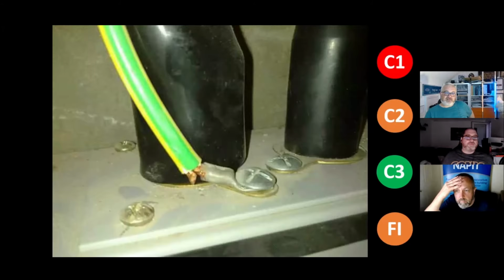I wouldn't be glanding it like that. I would be using a stuffing gland and taking it directly to the earth bar and then having a fly lead off of the banjo on the inside. But that is the CPC for the circuit. Well, if they calculated that as the CPC for the circuit and sized the cross-sectional area accordingly, even though they've got it on the armoured, don't they?